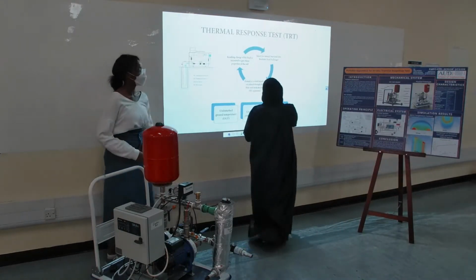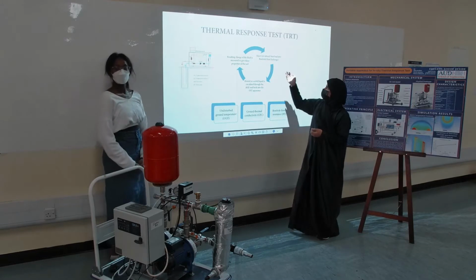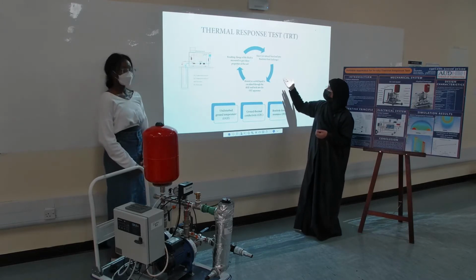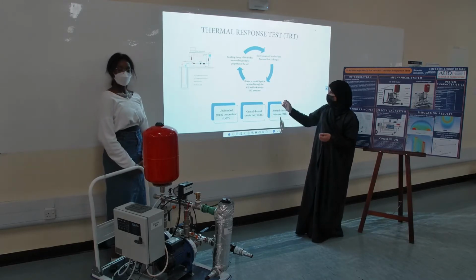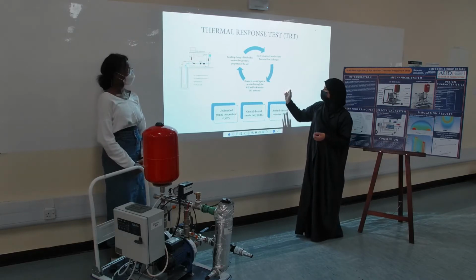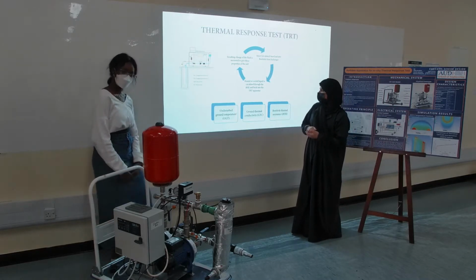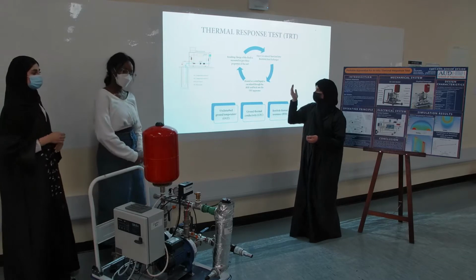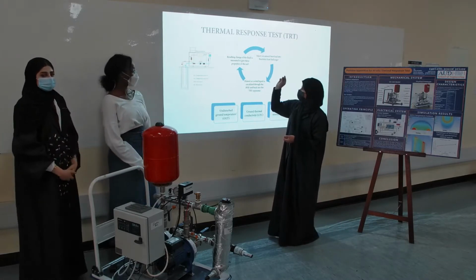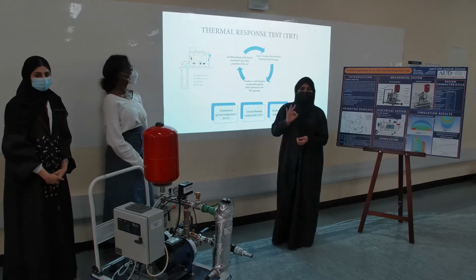Thermal response test: the first step is to inject or extract heat from the borehole heat exchanger. Then the heated or cooled liquid is circulated through the borehole heat exchanger and back into the TRT apparatus. Then the change of the fluid is measured to give three properties of the soil.